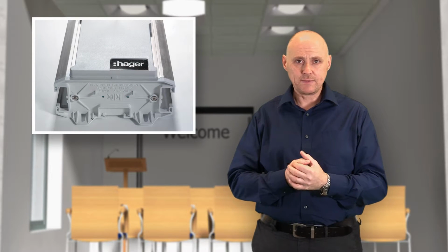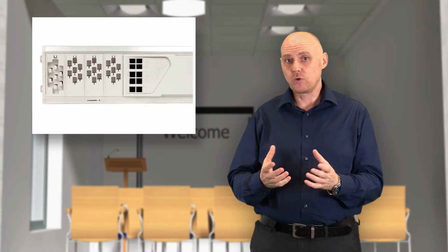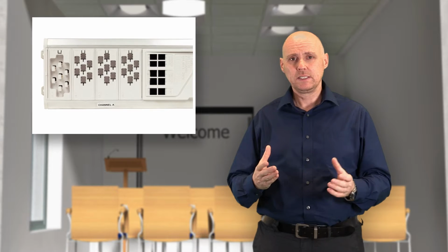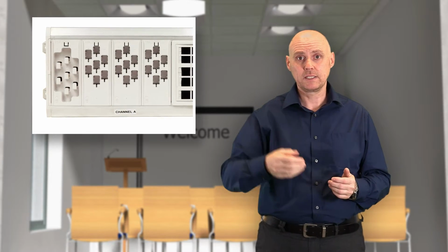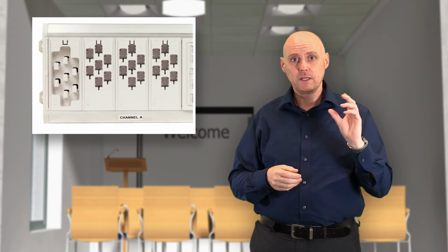Well, the LCM, the lighting control module, is a 4-zone or 4-channel system. So you can have different lighting control for the front of the classroom. You can have an input from dedicated lux sensors in the ceiling, so you can have dimmable lights or switch lights off with use of natural daylight, making the most of that natural daylight. You can also have a switch by the door, which obviously is needed, which can be on, off, dim, up and down.